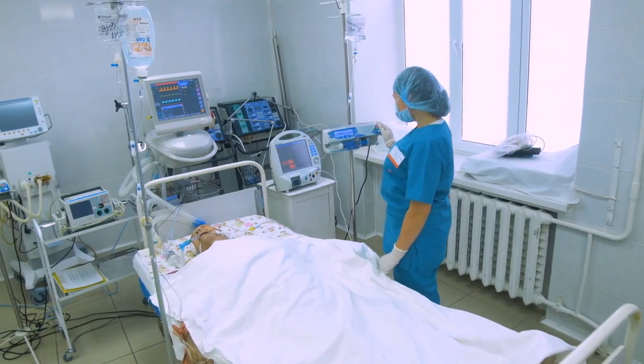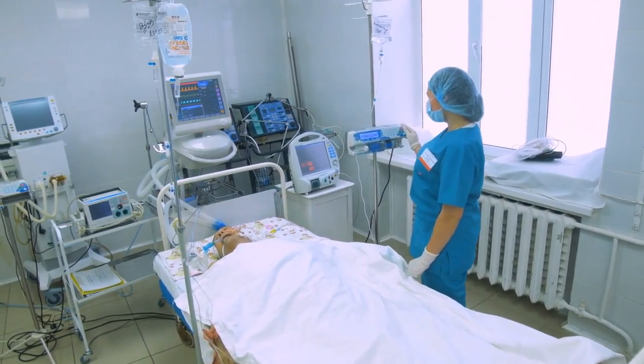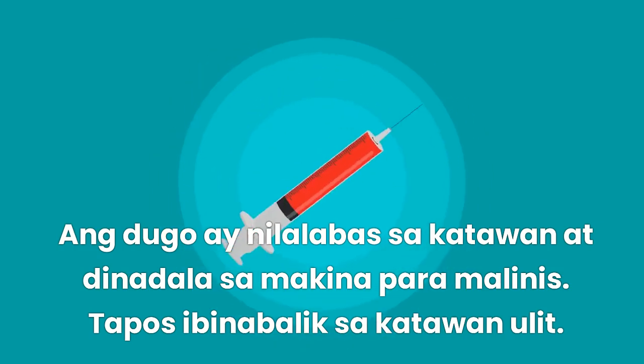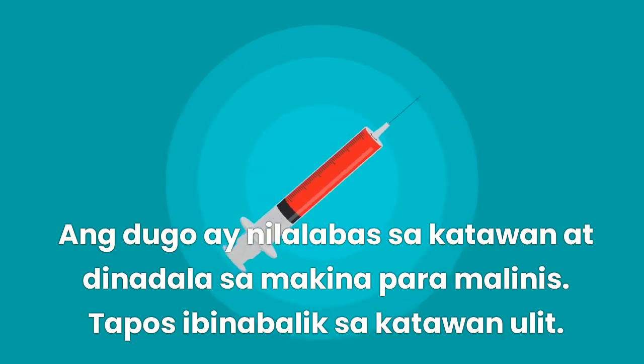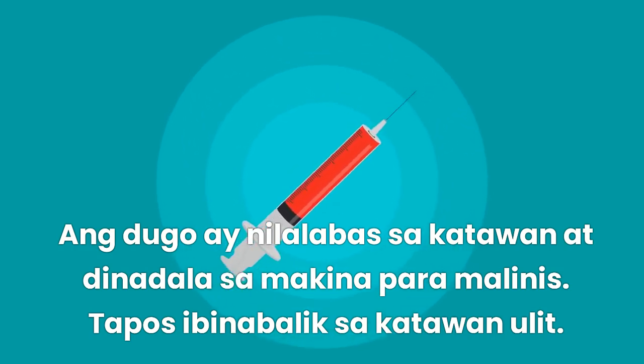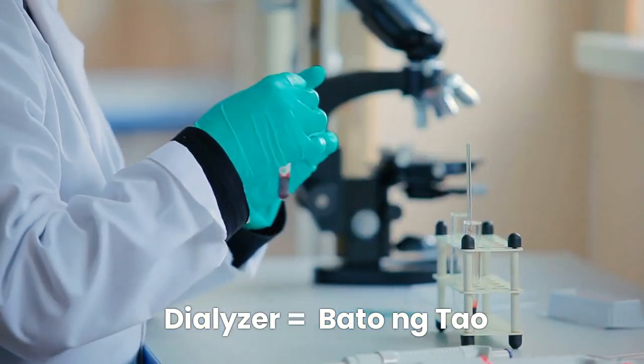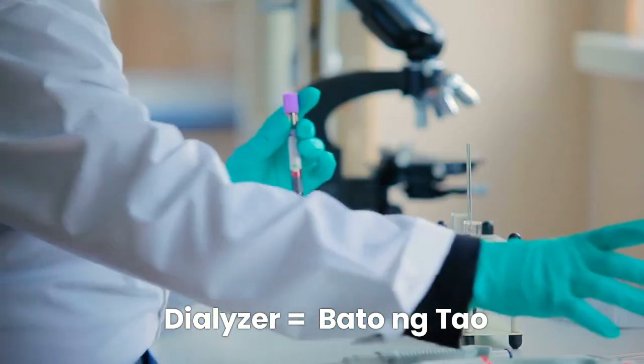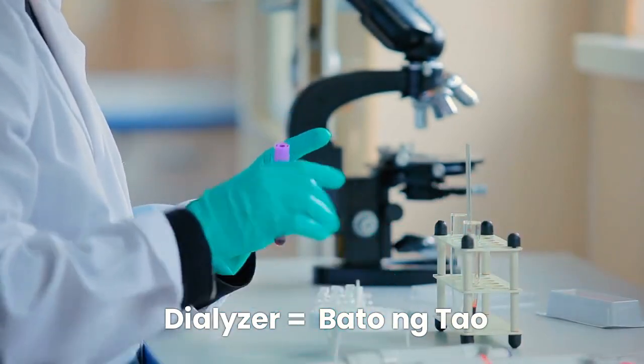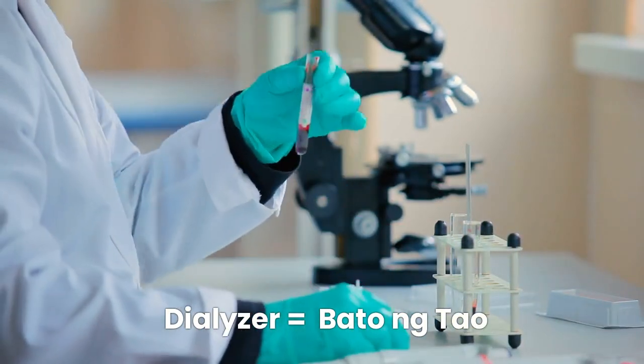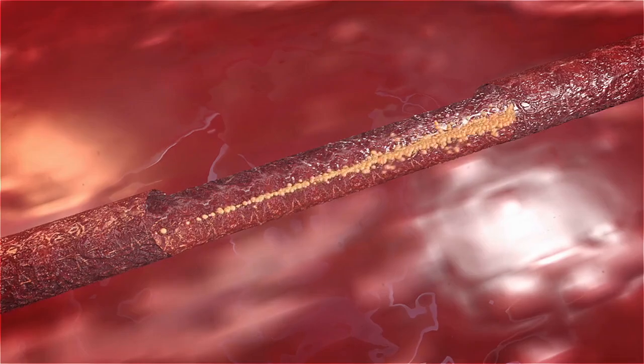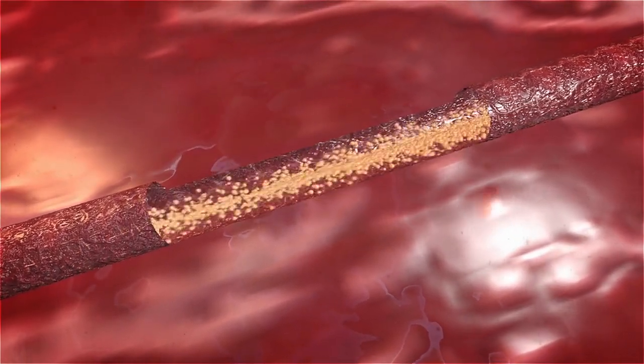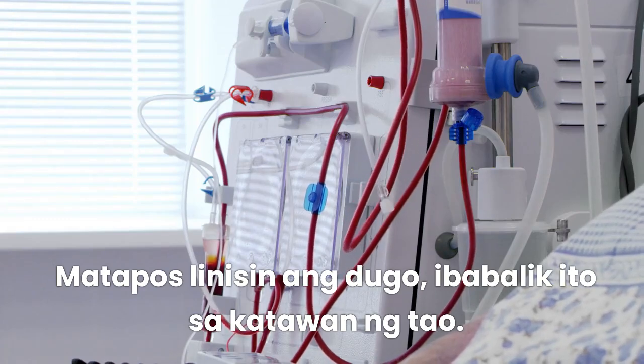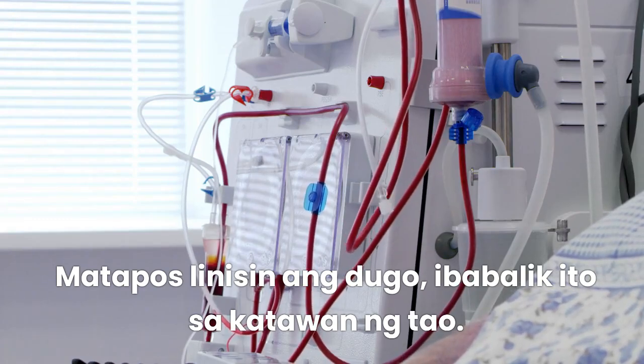Dialysis machine setup: the patient is connected to a dialysis machine. Blood is removed from the body via the vascular access and passed through the machine's dialyzer, which acts as an artificial kidney. Filtration: inside the dialyzer, blood flows through tiny hollow fibers while a dialysis solution, dialysate, flows outside the fibers. Waste products and excess fluids move from the blood into the dialysate through diffusion and osmosis. Return: filtered blood is then returned to the body through the vascular access.